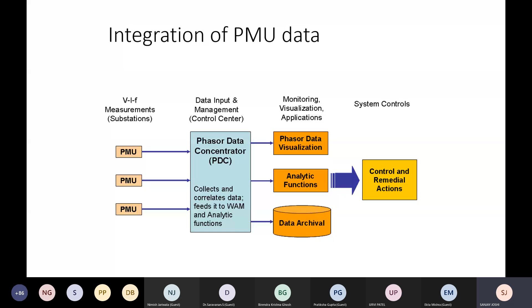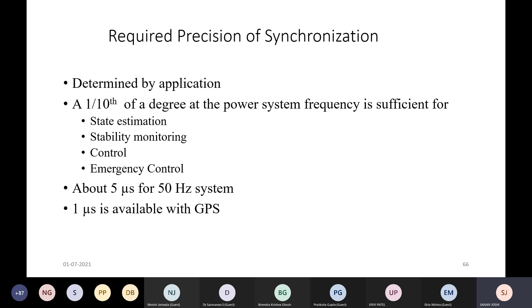Required precision of synchronization: 1/10 of a degree at the power system frequency is sufficient for applications like state estimation, stability monitoring, control, and emergency control. So the required precision is about 1/10 of a degree. In one complete cycle there are 360 degrees, and 1/10 of a degree precision is required. That comes to about 5 microseconds for a 50 Hz system, and the precision of synchronization given by GPS is 1 microsecond, which means that for all practical purposes the required precision is met if you employ PMUs and PMUs networks.